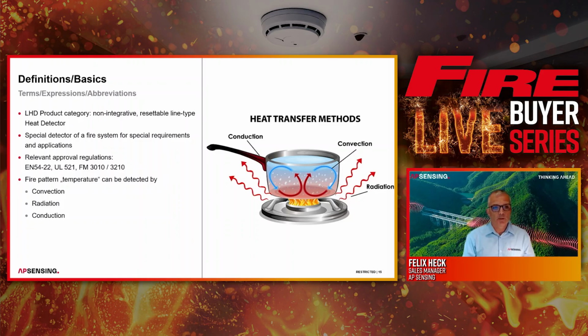And we can also measure conducted heat. That means, for example, on cable trays, we put the sensor cable directly on the cable tray and measure the temperature of the cable itself. Same with, for example, battery power stations or so. There we measure heat by conduction.